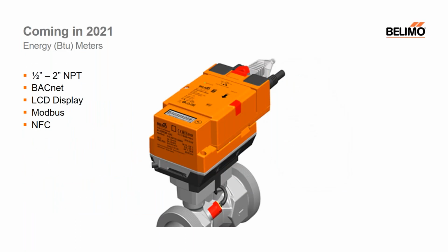However, coming out in 2021, we are going to introduce BTU meters. So initially, we're going to come out with a 1/2 inch to 2 inch inline BTU metering offering. It's going to be BACnet capable. It's going to have a LCD display. It's also going to speak Modbus, and it will be accessible via near-field communications as well.